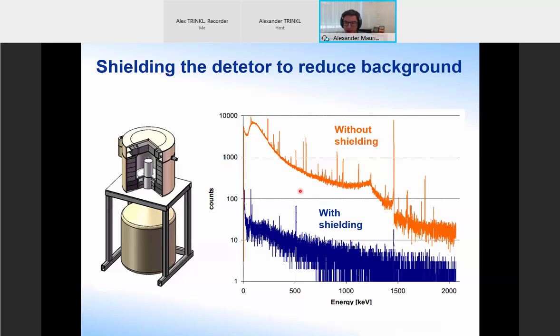And in the end you'll optimize, and you'll see here on the right side a typical spectrum, how the spectrum of a detector might look if you just measure the background without shielding and with shielding. You see we reduce the background noise to the detector by a few orders of magnitude. This is noise that you don't want to have in your spectrum. So that's some of the things you might have around your detector to keep it happy, so cold and low background.